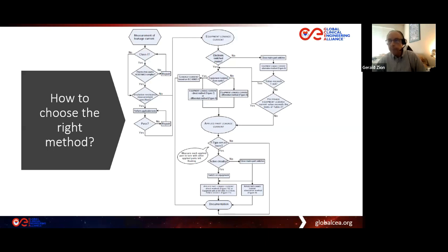So what might that be? Well, in particular, the time when you would use something other than direct or differential methods would be if there is no on-off switch or there are active circuits in the medical device. And so no on-off switch can apply to some kinds of electromedical devices that are used in physical therapy, where as soon as you plug it into the wall, it is turned on. So current is going to flow in a greater amount than if it was not turned on. So in that case, you would use the alternative method. And that is the clearest example that I can come up with to make it simple for you to understand.